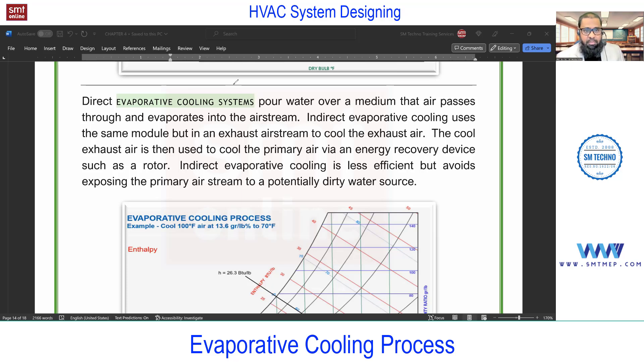In evaporative cooling there is no condensation - only sensible cooling. You cannot expect latent cooling. That's the reason it is applicable in desert areas. In areas with humid conditions you cannot achieve the required comfort because in humid areas it is required to extract moisture, reducing the humidity. In desert areas this works efficiently because of low humidity conditions - decreasing temperature and increasing RH are both requirements satisfied by evaporative cooling.